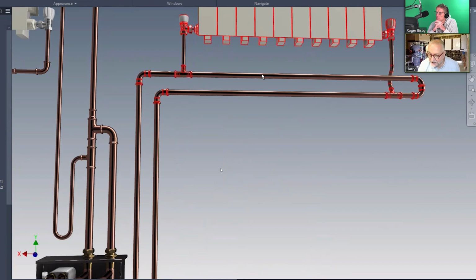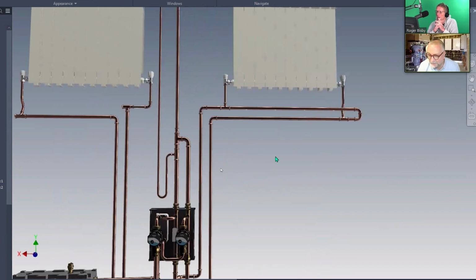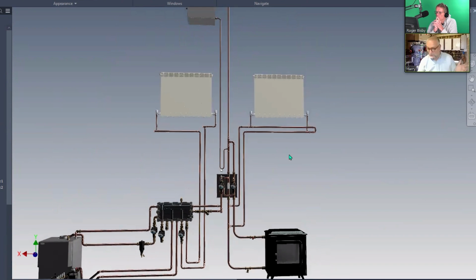I put a T here, and teed the two of them together with a valve barely open. The valve is just enough to let any air trapped in this pipe rise up into this pipe, and then you have one vent on the positive side of the pump. As I say, there isn't a fundamental difference between sealed and open systems, but you still have exactly the same issues, they're just hidden better with a sealed system.